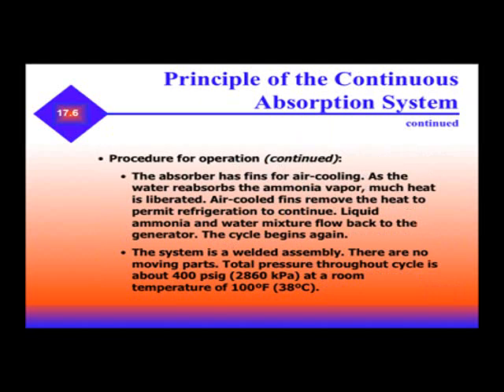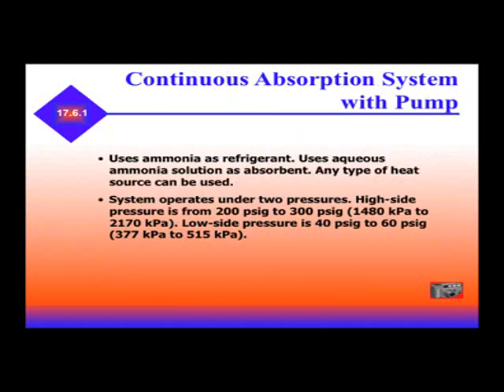The system is a welded assembly with no moving parts. Total pressure throughout the cycle is about 400 psi at a room temperature of 100 degrees. It uses ammonia as a refrigerant and aqueous ammonia solution as an absorbent. Any type of heat source can be used. The system operates with a pump under two pressures: high side pressure is 200 to 300 psi, and low side pressure is 40 to 60 psi.